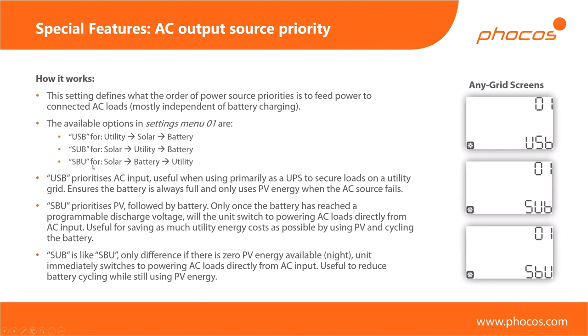We have Utility-Solar-Battery (USB), Solar-Utility-Battery (SUB), and Solar-Battery-Utility (SBU). Starting with USB — Utility-Solar-Battery — this is the scenario where solar isn't that important, or you have a very small PV array just to keep the battery topped up. The reason you're using the anygrid is to handle scenarios where the grid fails. Guaranteed power is more important than cost. You prioritize the grid as first priority, use solar if the grid fails, and then battery to make up any shortfall.